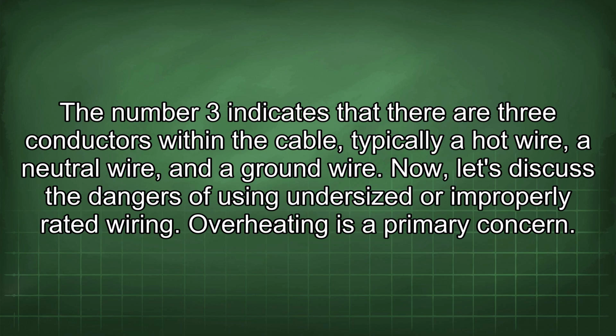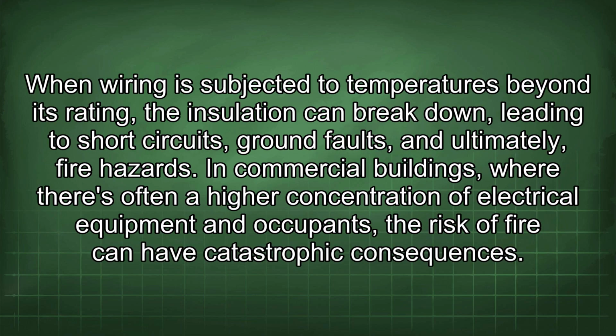Now let's discuss the dangers of using undersized or improperly rated wire. Overheating is a primary concern. When wiring is subjected to temperatures beyond its rating, the insulation can break down, leading to short circuits, ground faults, and ultimately, fire hazards. In commercial buildings, where there's often a higher concentration of electrical equipment and occupants, the risk of fire can have catastrophic consequences.